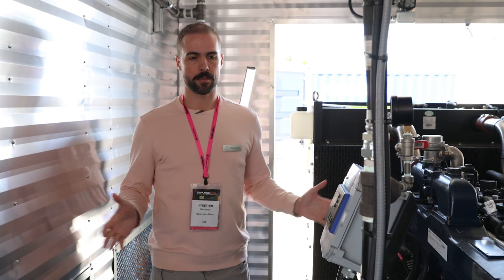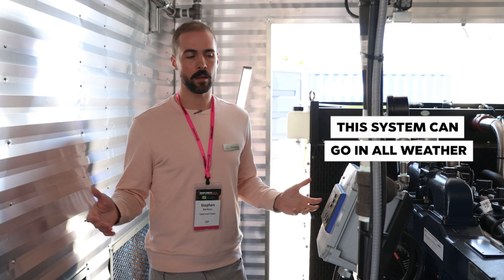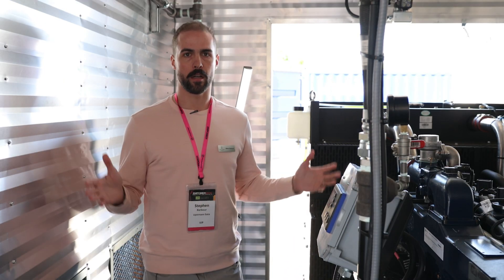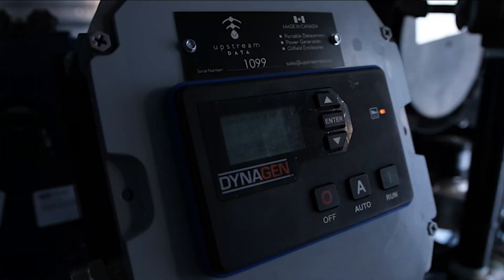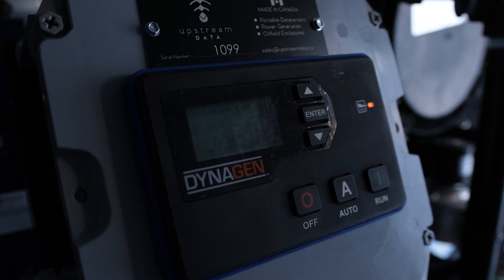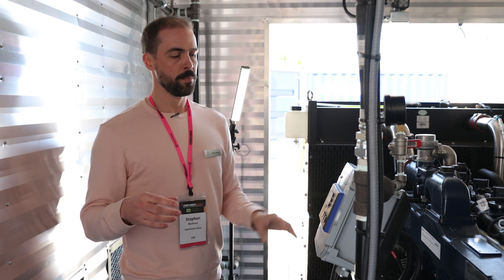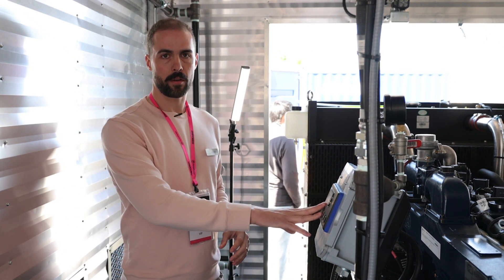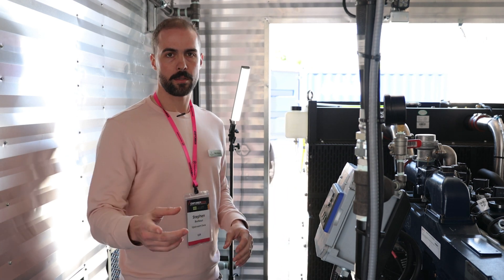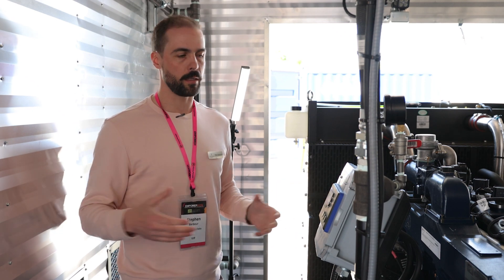If you're operating this unit, we make this room nice and spacious. This is a system that can go in cold weather — we're based in Canada — so it's a nice walk-in building. When you're servicing the engine or doing maintenance, you're in a nice environment, not exposed to the elements. Normal engine control panel — we use Dyna Gens, some customers use Deep Sea controllers. We tie into our load sync control system on the other side, which reads the engine data coming out of the engine controller into our main brain that will automate your entire product.